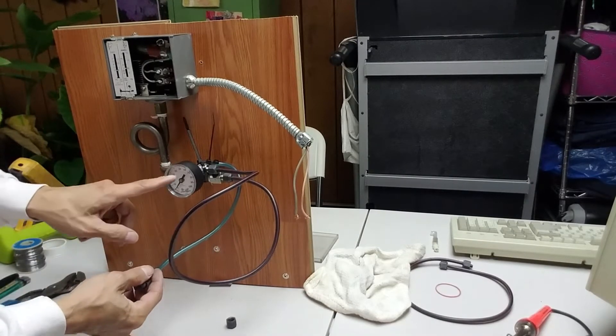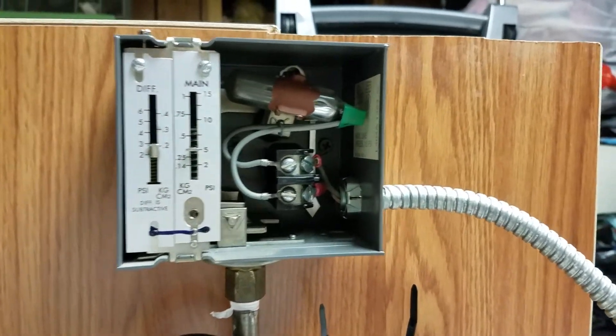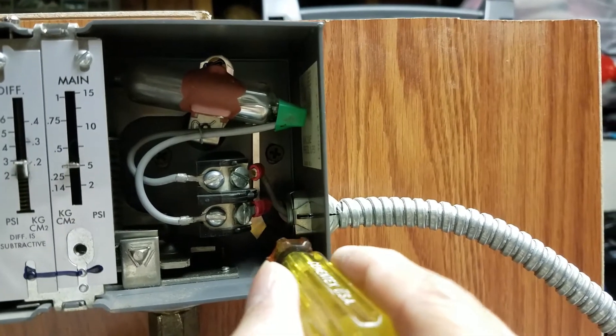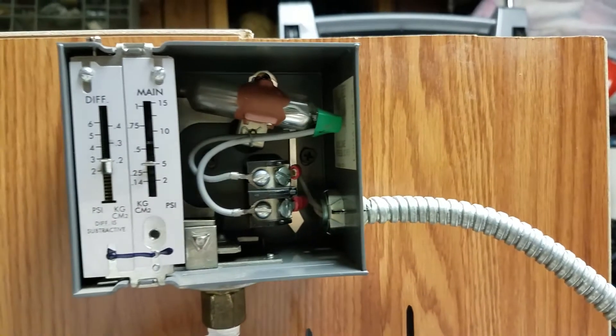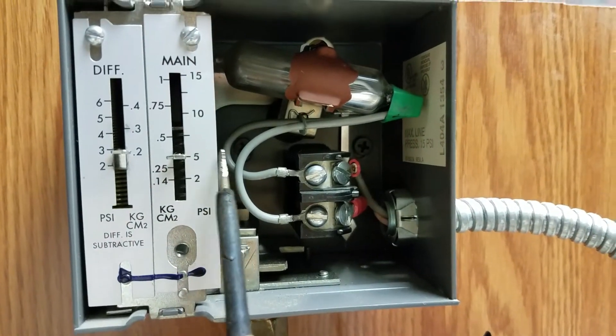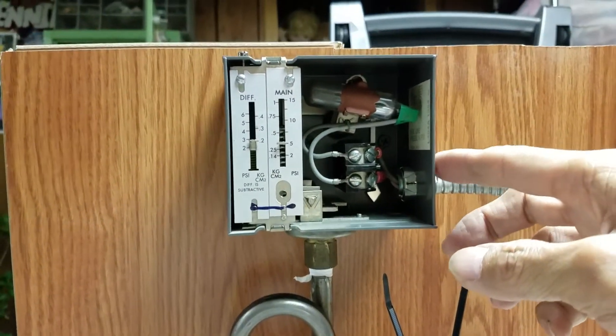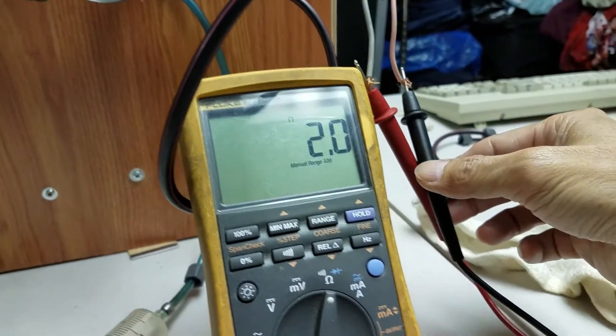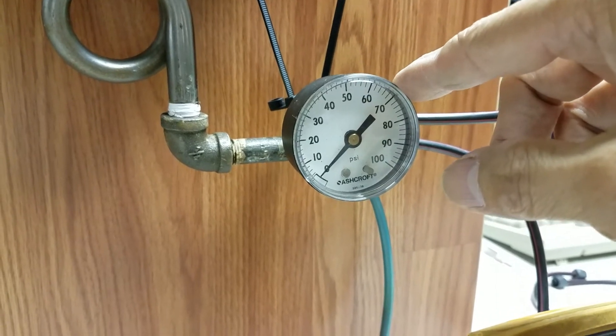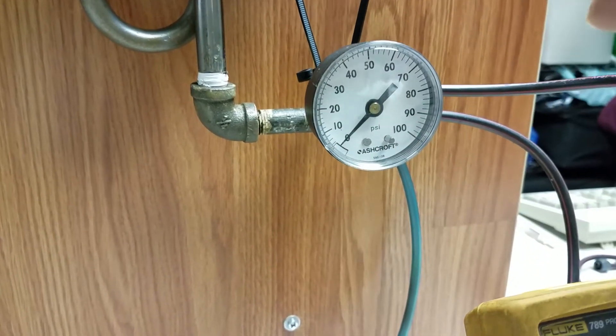I remount the pressure gauge. If you don't have the level adjustment for perpendicular to the horizontal, you can look inside of the switch, it has a little balancer. You can follow this. The main set at 5 psi. And the differential is 0.2 psi.